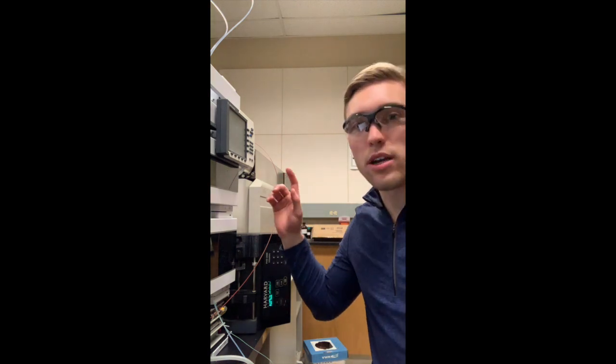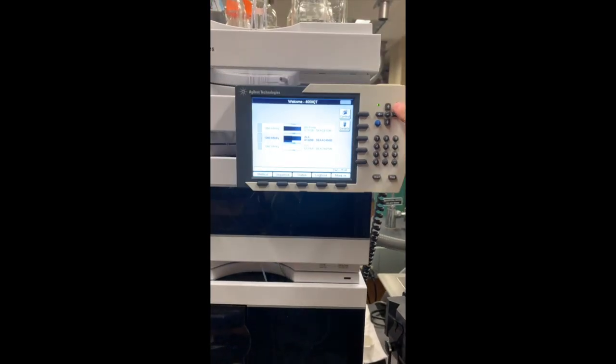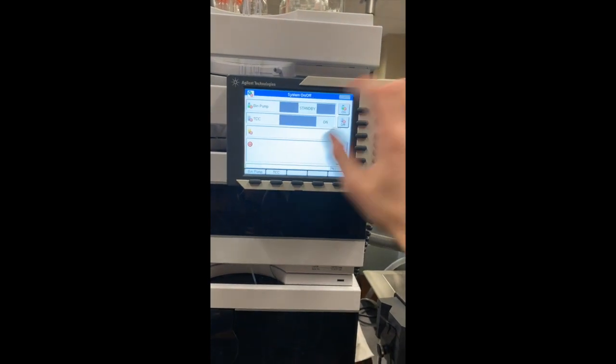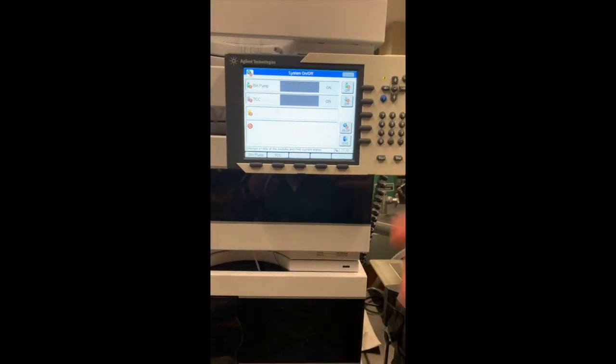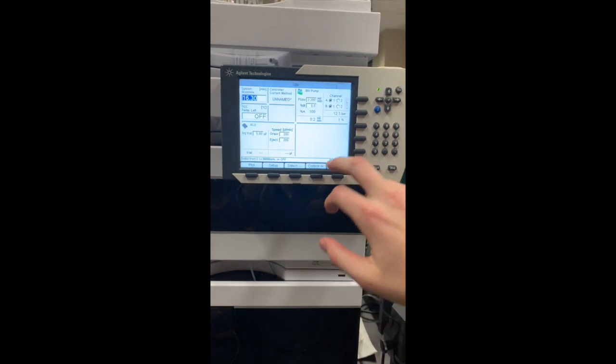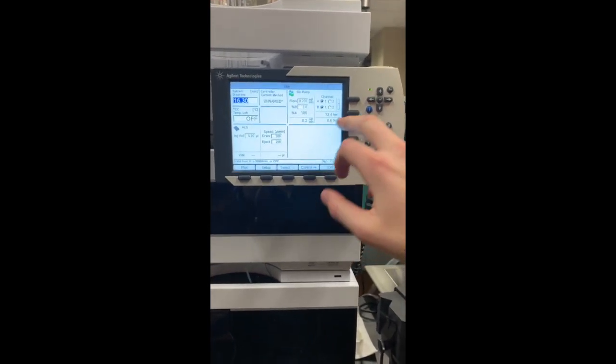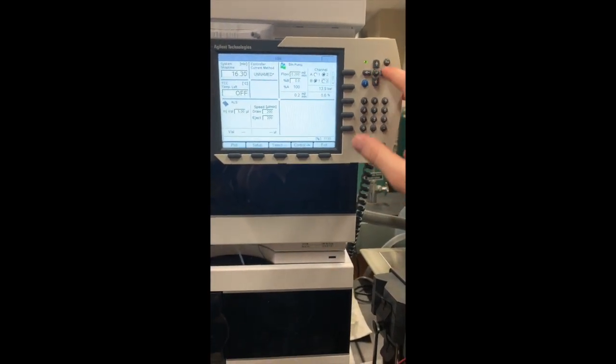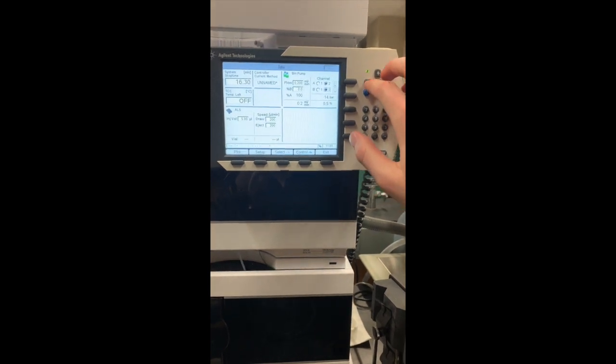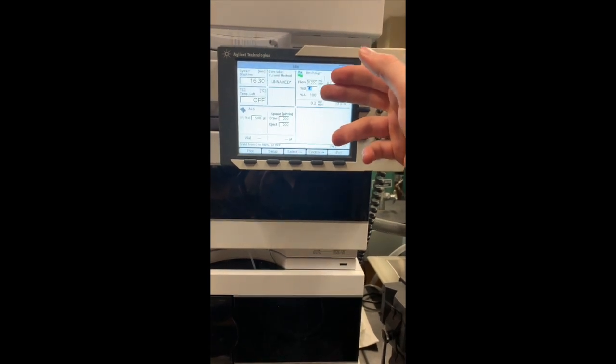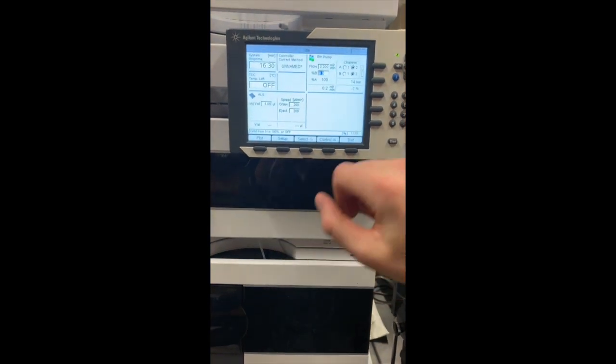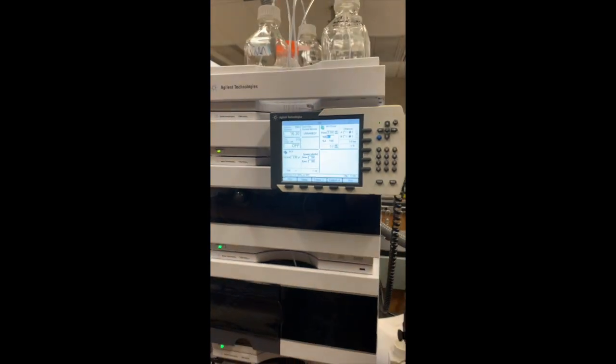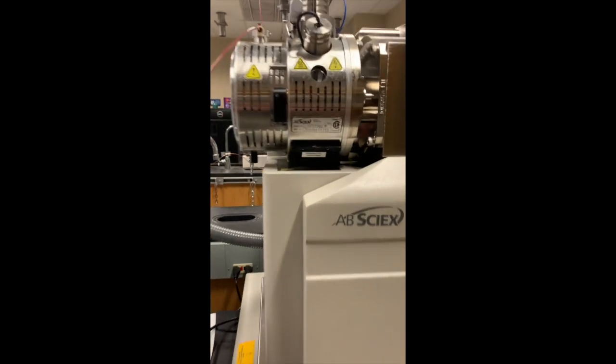So I'm just going to show you how to do that using this little system right here. So here we can just go to controls, system on off, and we want to turn the bin pump to on, so we can press right there. Now this will start the flow of solvent. We want to make sure that our solvents that we're flowing are actually the correct solvents. Here it's set to A1 and B1. If you can recall I would like A2 and B2 so I'm just going to set that. And if you want to change the composition that you're flowing through your column you can change it using percent B and percent A here. Now a good way to check to make sure that solvent is flowing through your system through your column and into the mass spec is actually to look in this window right here and you should be able to see drops of solvent falling from the needle tip.